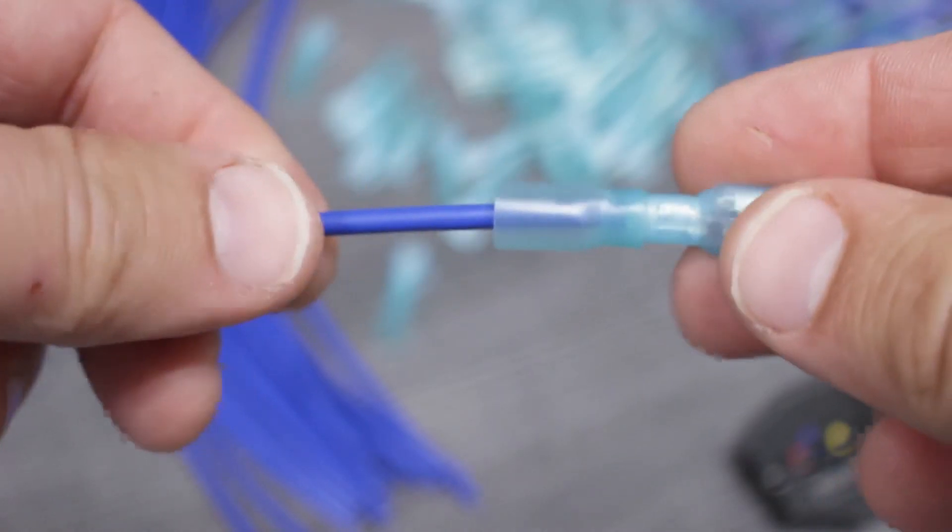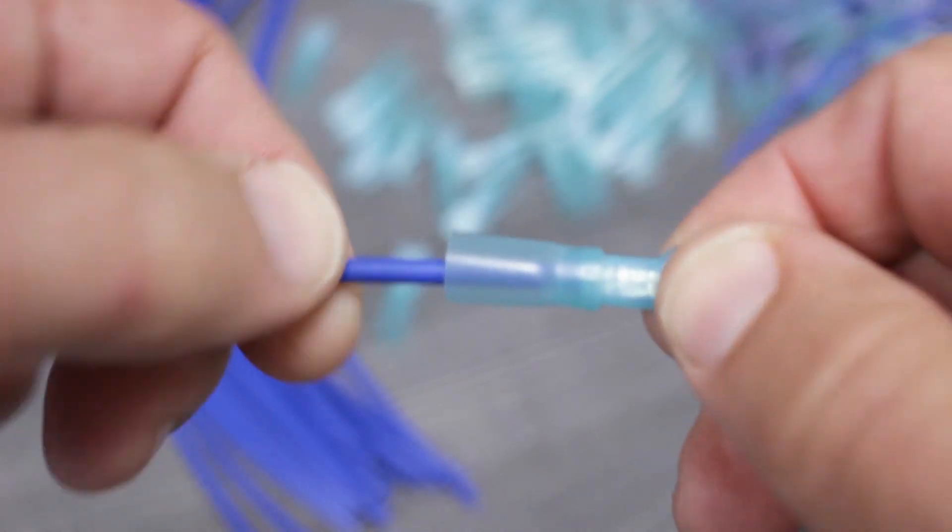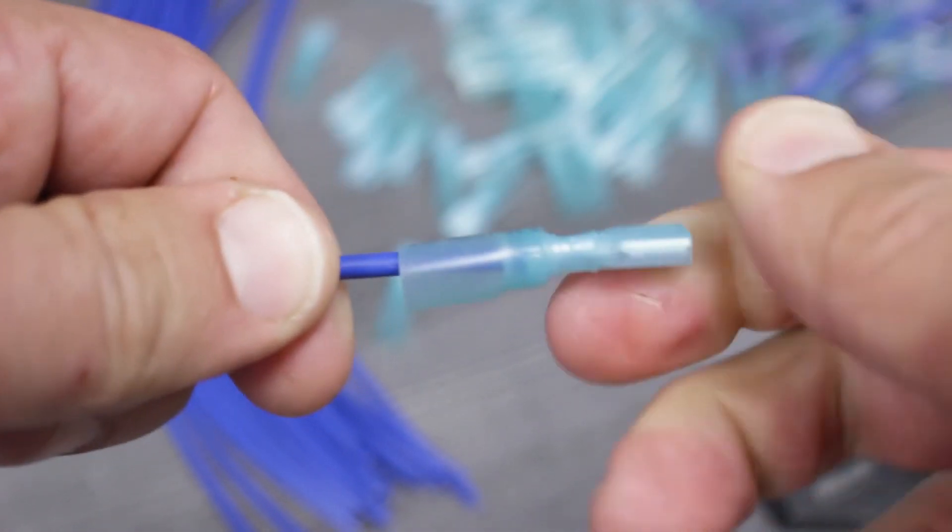To ensure a solid connection, perform a tug test by gently pulling from both sides of the connection point, paying careful attention for any movement or give. Since it didn't move, we know this connection point is solid.